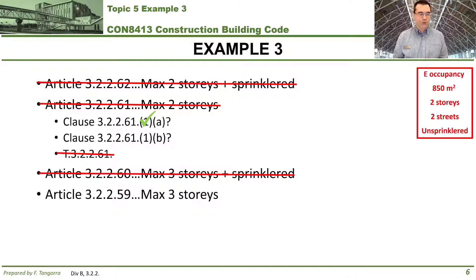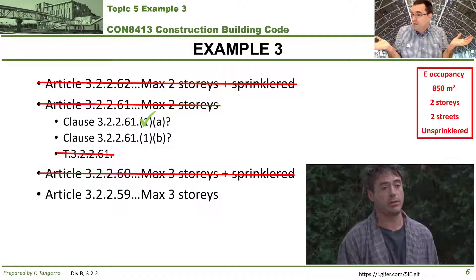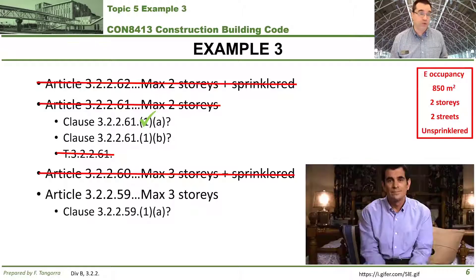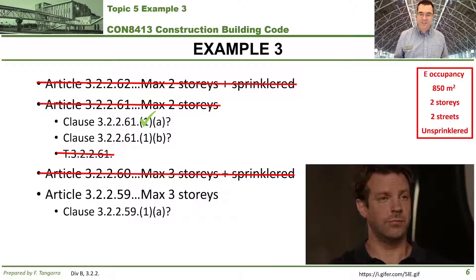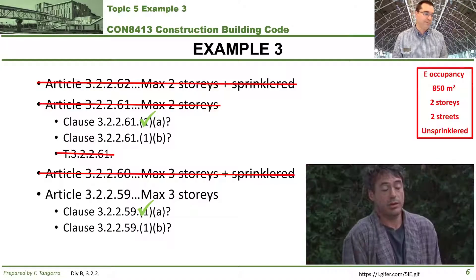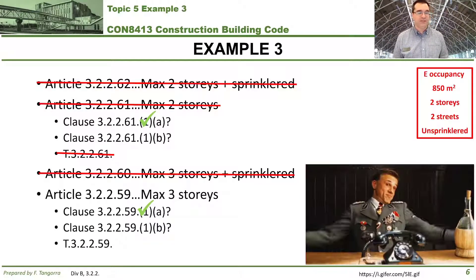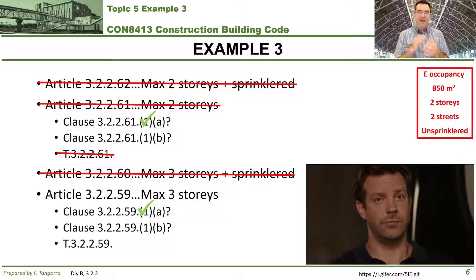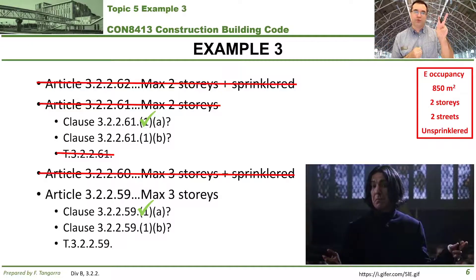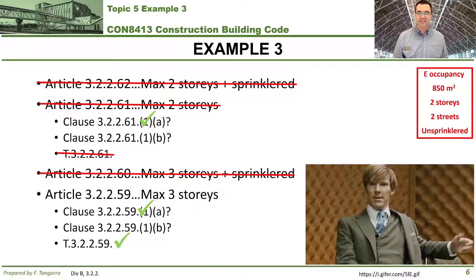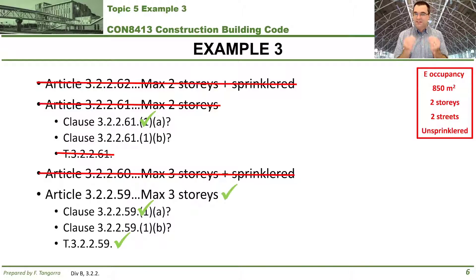The next article is 3.2.2.59, titled Maximum Three Storeys. Could that work? Maybe. We read the whole content of this article. Clause 3.2.2.59.(1)(a) applies. Then we move to Clause 3.2.2.59.(1)(b), which sends you to Table 3.2.2.59 — a table with number of stories, how many streets the building is facing, area, and so on. Does our building at two stories, facing two streets, and at 850 square meters fit within the requirements? Yes, it does. Article 3.2.2.59 is applicable.